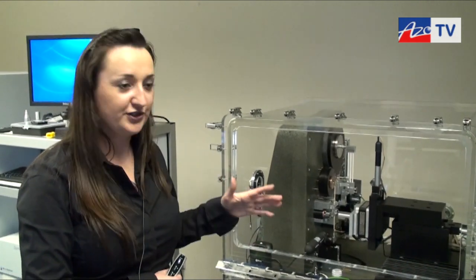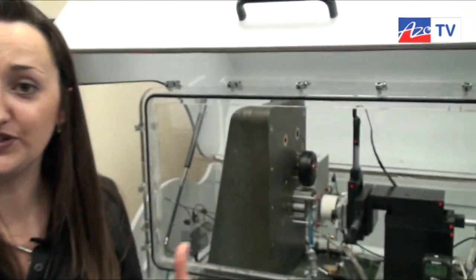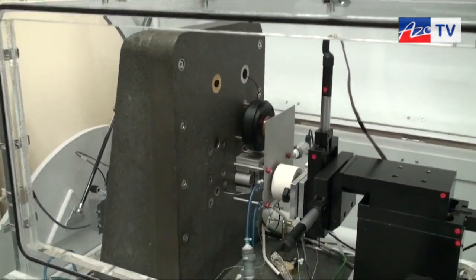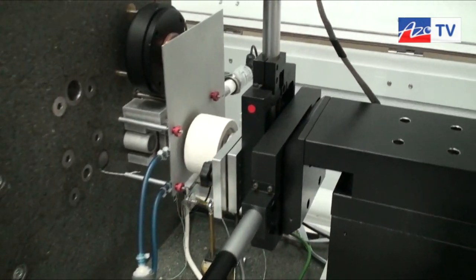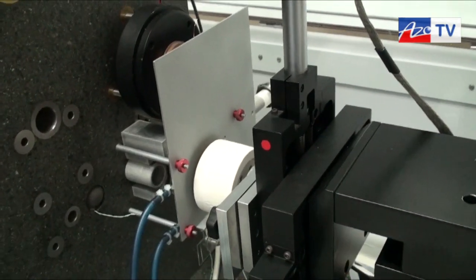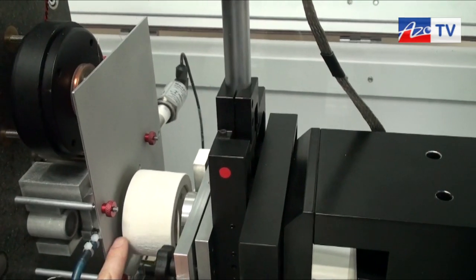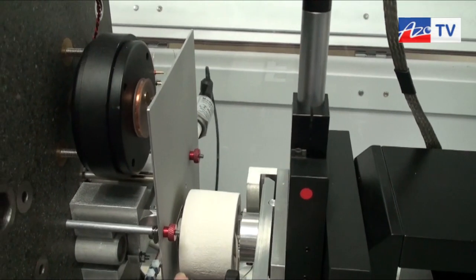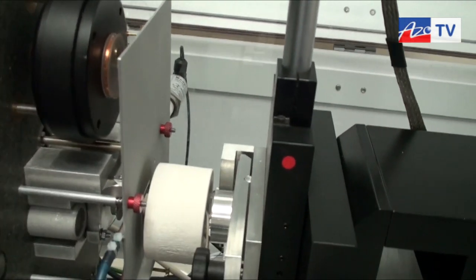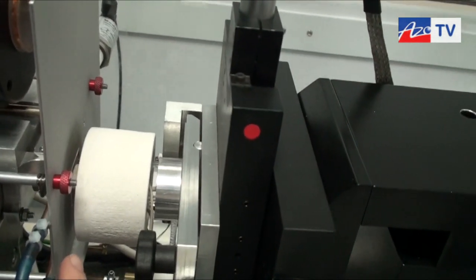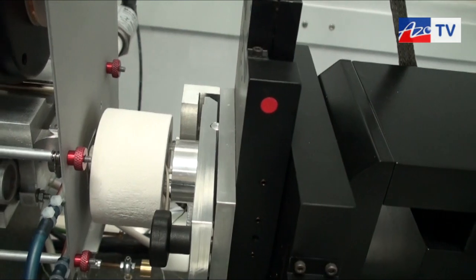An instrument that's being set up specifically for hot stage measurements. This instrument here can work at temperatures up to 750 degrees. So I can point out the hardware that we use. First of all, it's in the purge box, same as the one we saw earlier. Here on the right hand side, this is the sample stage. And you can't really see it very well, but the sample is just mounted in there. And the indenter is on the left hand side with its own separate heating system.